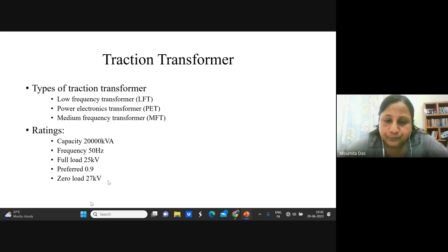The rating of the transformer will be 20,000 kVA. The input it can take can be 25 kilovolt at 50 hertz, or 15 kilovolt at 16.7 hertz. The preferred power factor is 0.9, and at zero load condition it will be around 27 kilovolt. So basically the input voltage will be 27 kilovolt.